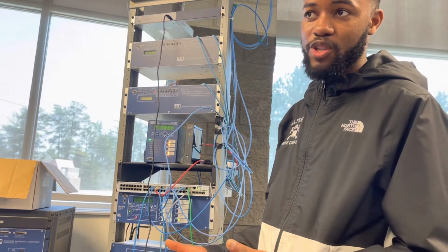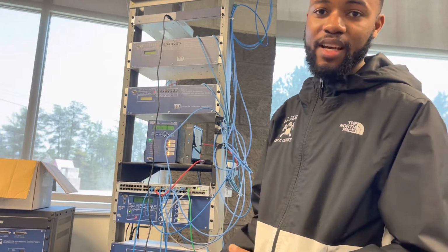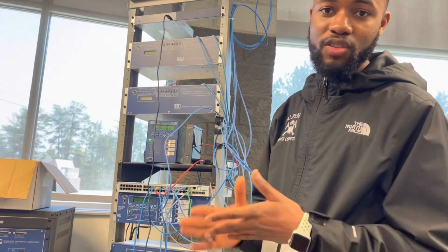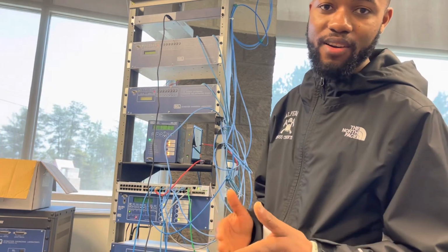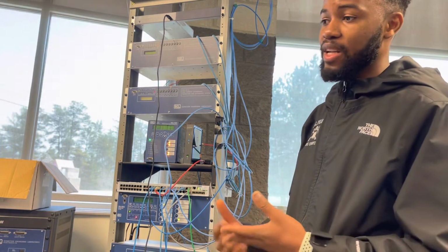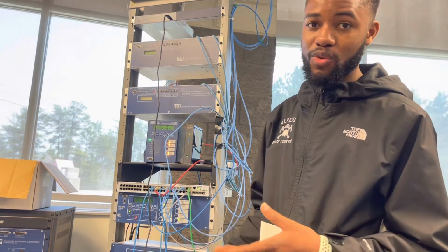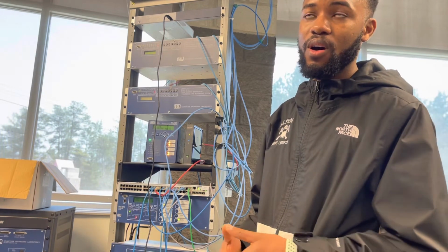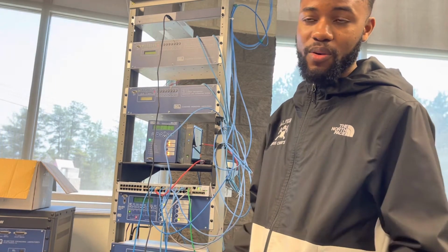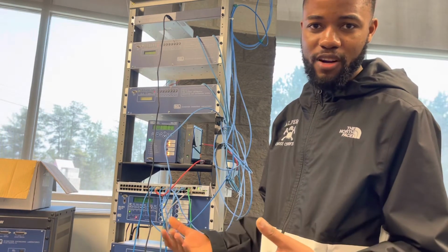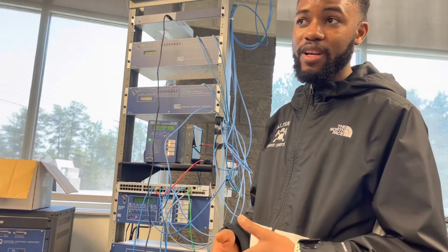So we can set up the ratio, and then we can monitor the current and the voltage and whether they are in phase or out of phase, and whether they are lagging or leading. So we can monitor everything from here. And also with the SEL relays, you can connect them through serial communication, or you can connect them through Ethernet. So you can control them through the Wi-Fi. And so we have both of those set up on our SEL relays.